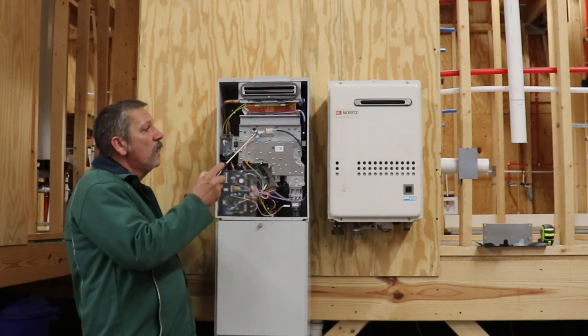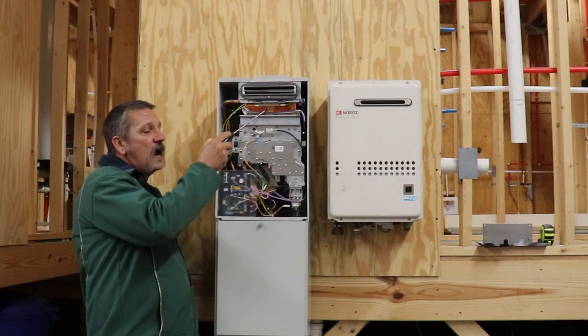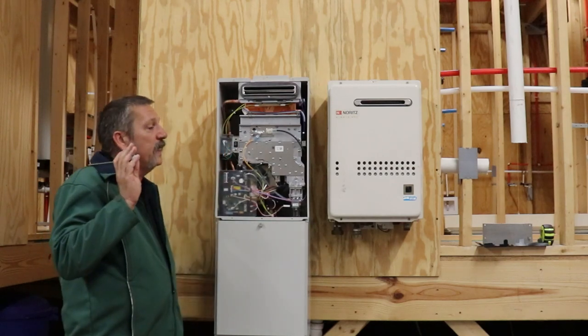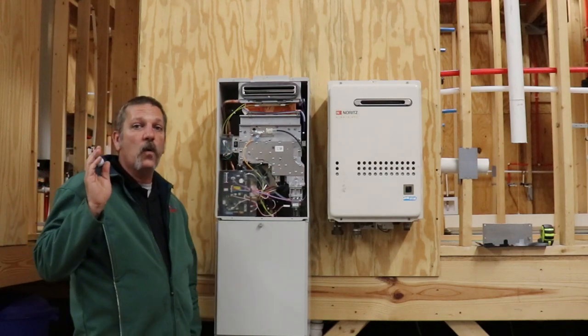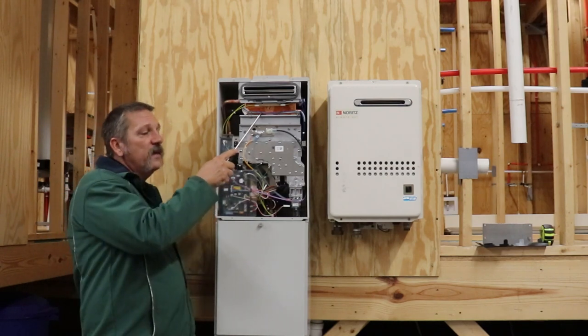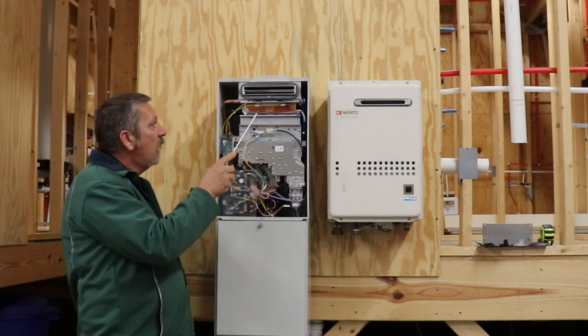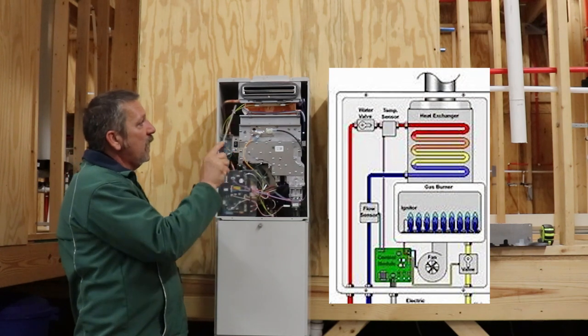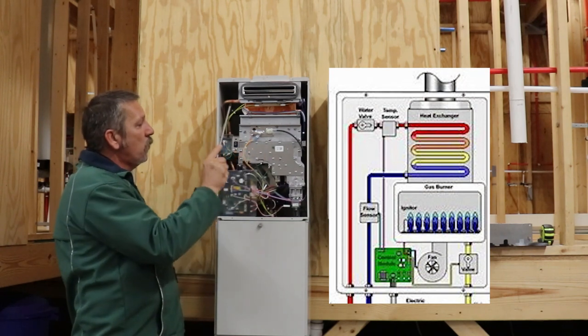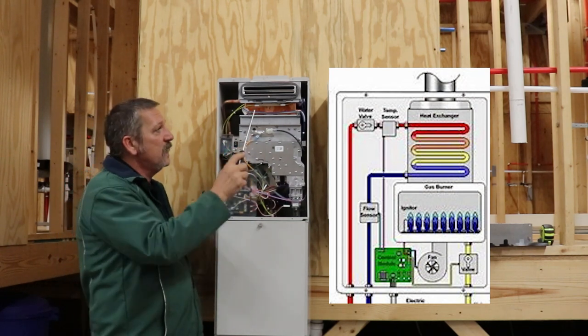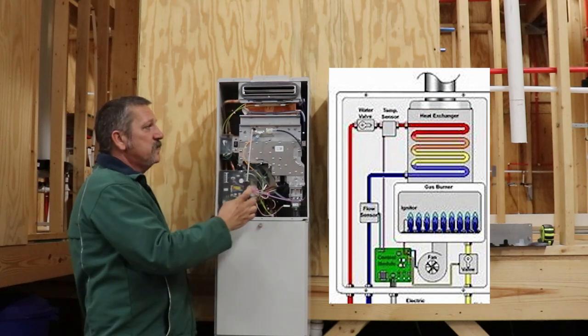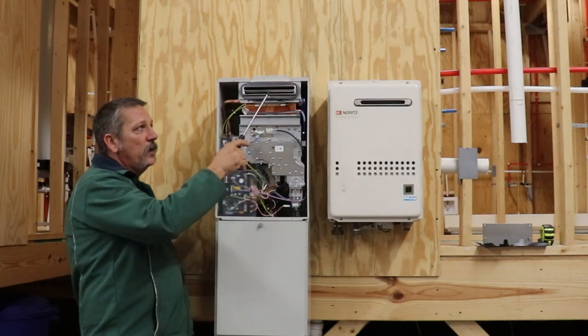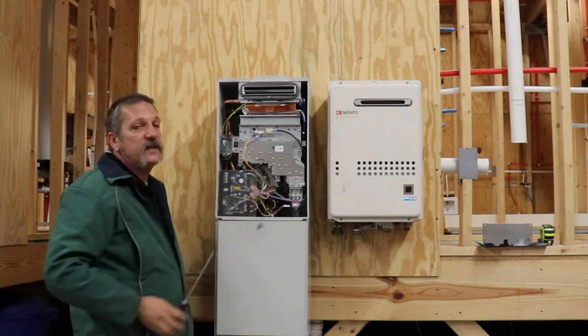All right, so above your combustion chamber, you're gonna have your heat exchanger. Some people call that the core, copper core up here. That's where all the magic's happening. Your cold water's gonna come in, and it's got tubes that loop back and forth, back and forth, back and forth, and it's got little vanes on it. As the hot air rises up through there and then comes out the exhaust, it's gonna heat that water.